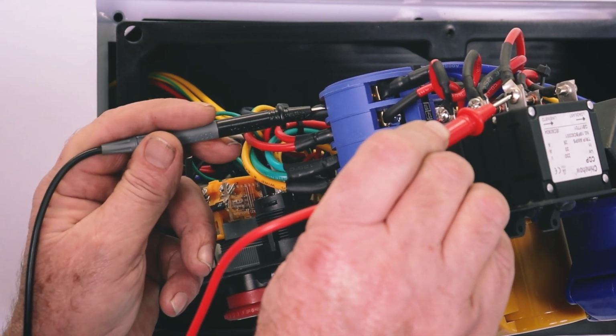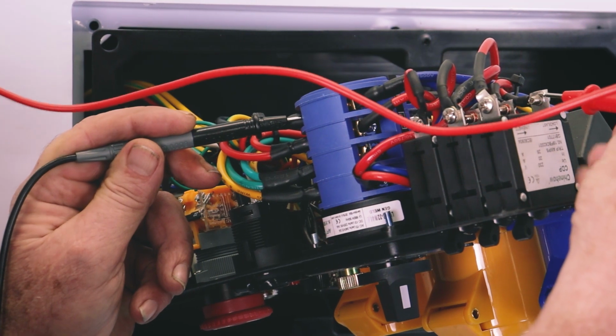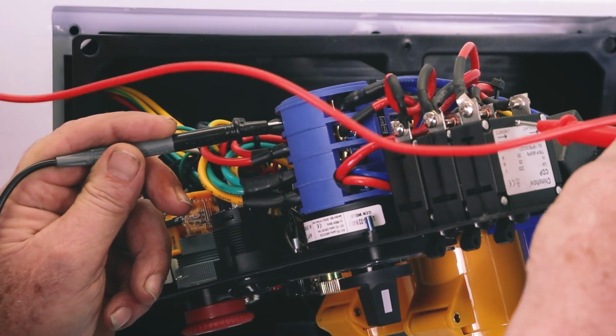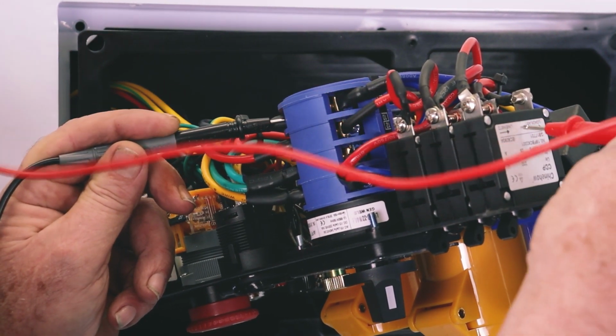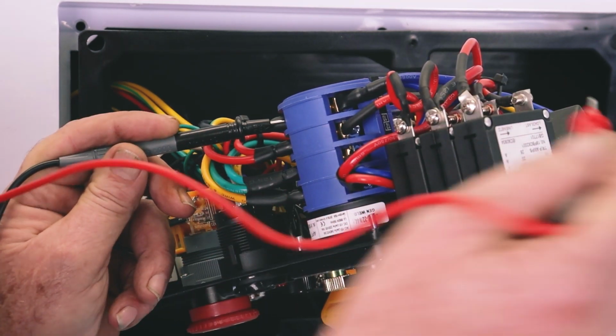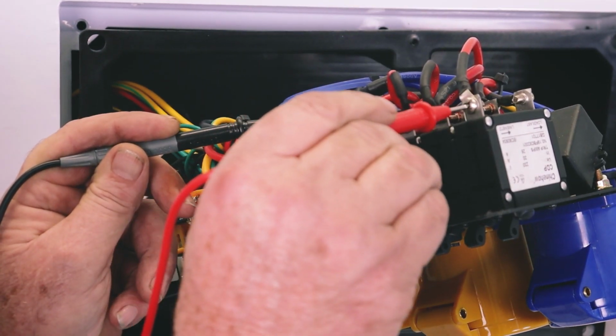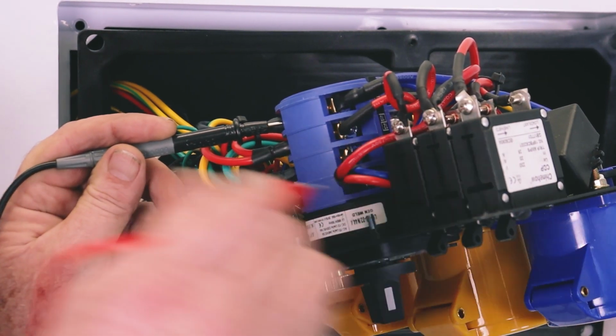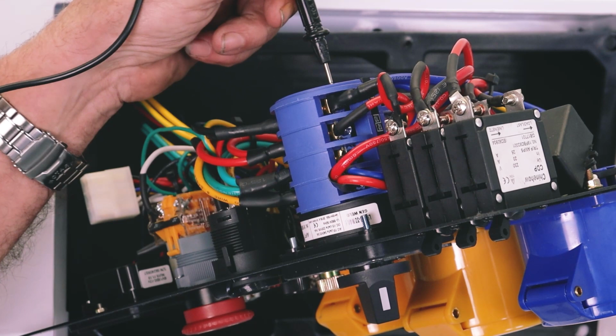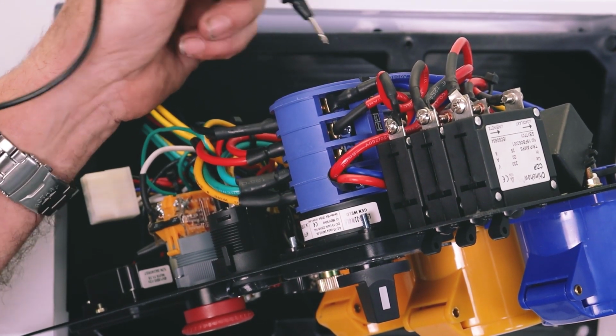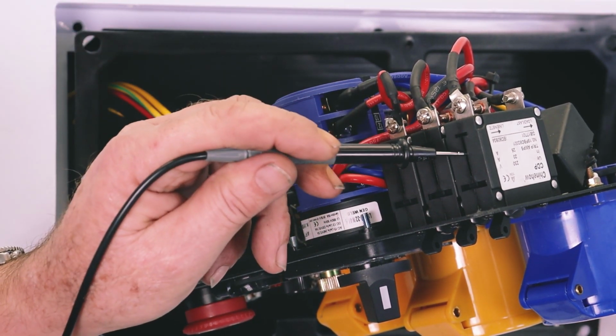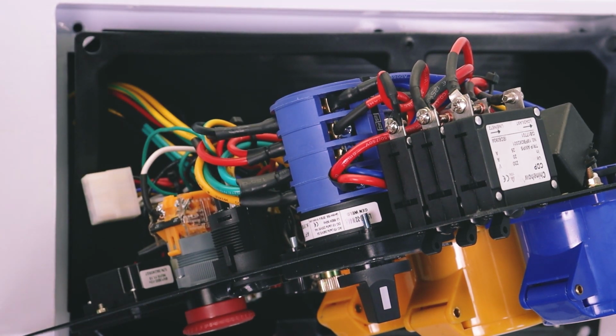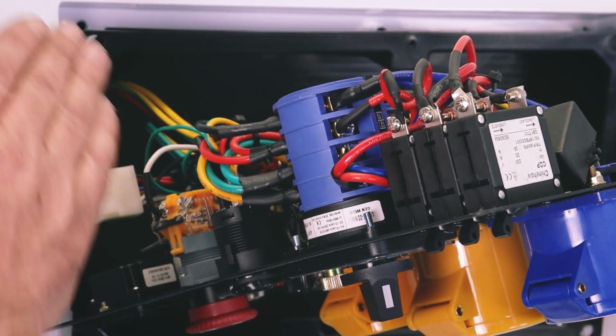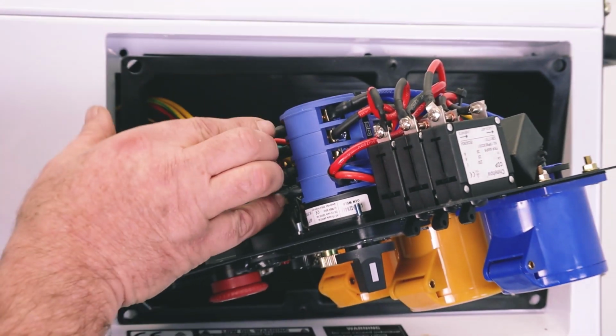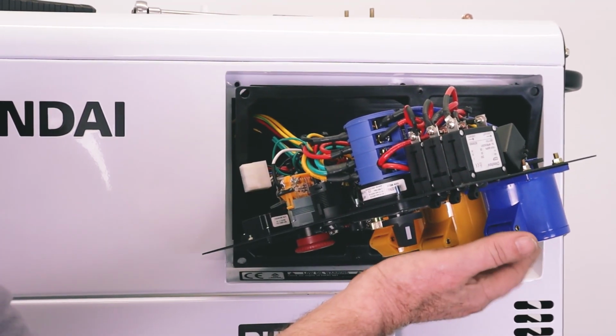If I get 230 there, but I don't get 230 on this side, it suggests a problem with this switch here. So that tells me I need to replace this switch. Everything's happy. If we've got 230 here, but not to here, it's the switch, or the switch isn't switched on, obviously. So we've shown how to test the changeover switch to make sure that's throughputting, and the circuit breaker to make sure that's throughputting. Okay, so that is the scenario if the problem is that we've got voltage here, but not coming out of the socket underneath.